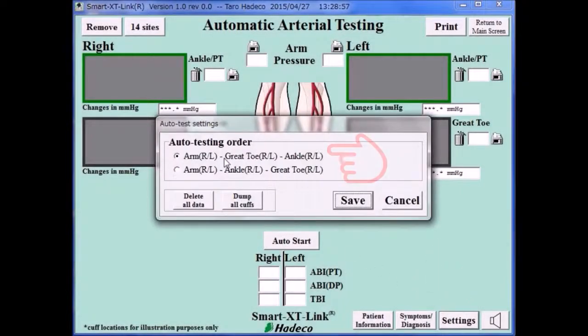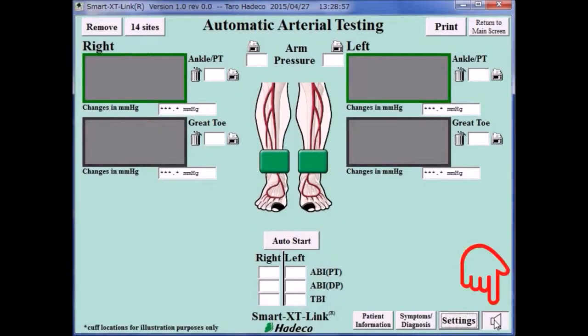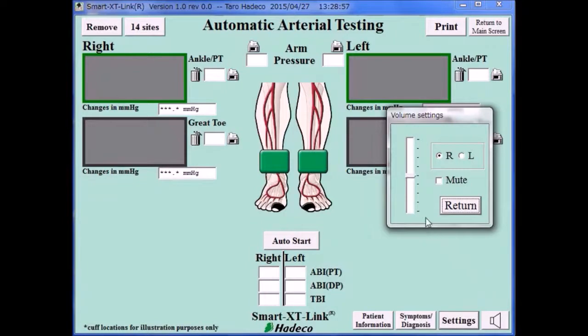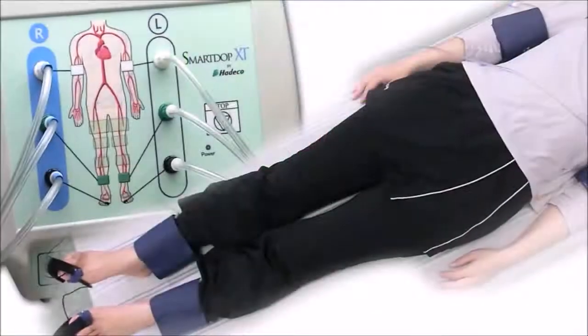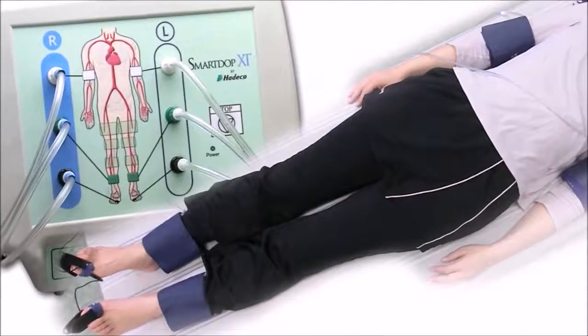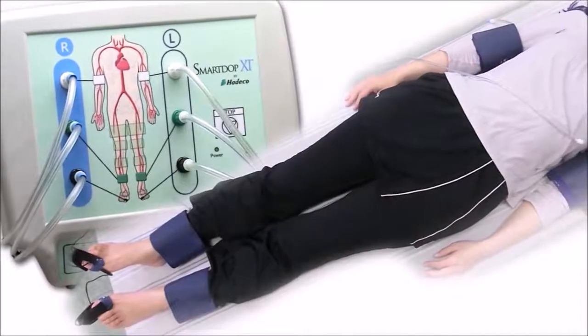Click Settings and select Auto Testing Order from 2 types of order for leg testing. The first order is normally recommended and click Save. Click the sound icon to control the PV sounds. You can select R or L side from where pulse volume sounds come out. Move the slider to adjust sound volume. Now, make sure all the cuffs and probes are connected correctly, and then preparation is done.